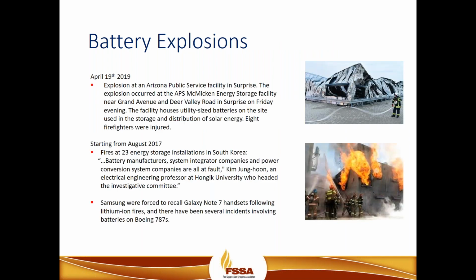These type of events are occurring on a more common basis. Of course, probably the most current and tragic fire that we've experienced in energy storage systems was the APS fire out in Surprise, Arizona. In this particular application, the building was a total loss. First responders and firefighters were on site and fighting the fire for at least maybe 3 hours before the building exploded. And really, this became a critical event when the firefighters looked to breach the building. And we'll talk more about what occurred and how that incident happened.